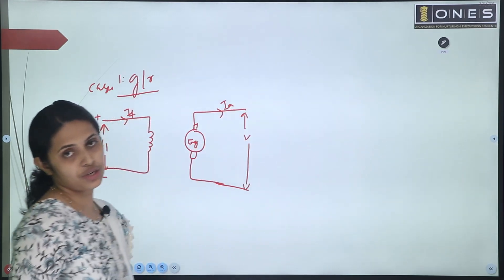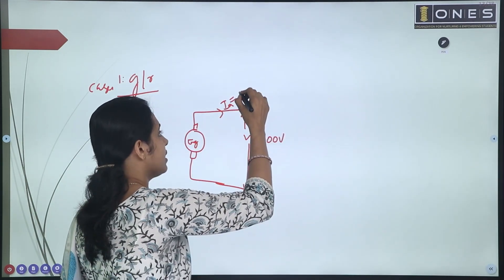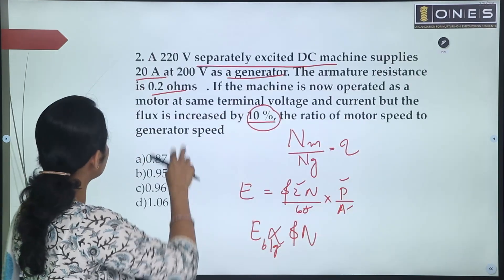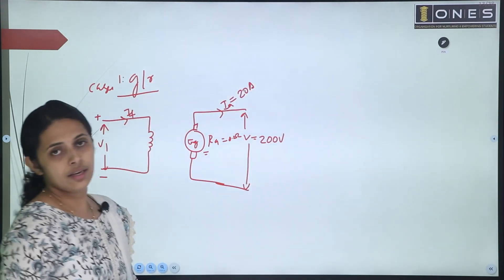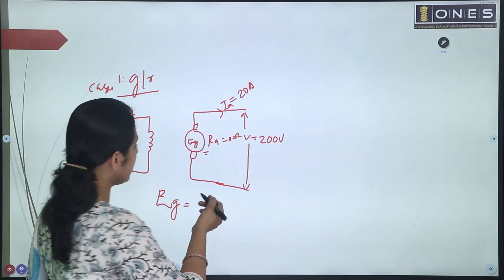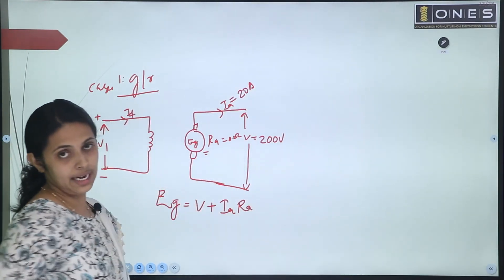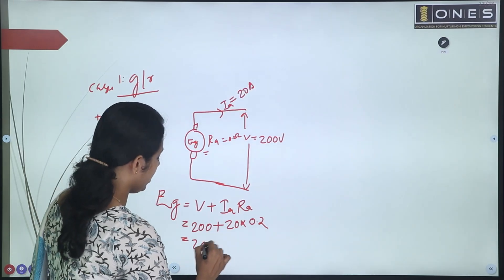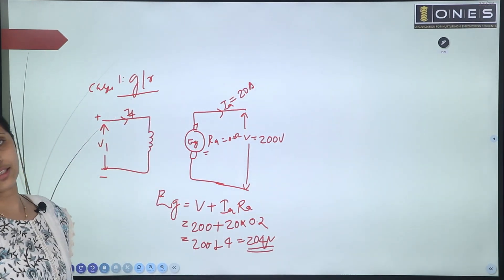The armature current is 20A and the terminal voltage is 200V. The armature resistance is 0.2 ohms. First, we calculate the generated voltage EG for the generator mode: EG = V + IA × RA = 200 + 20 × 0.2 = 200 + 4 = 204V.